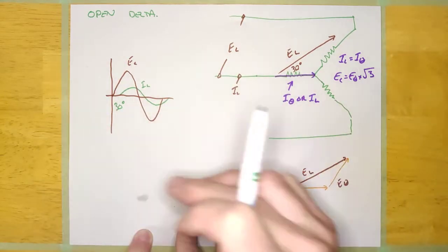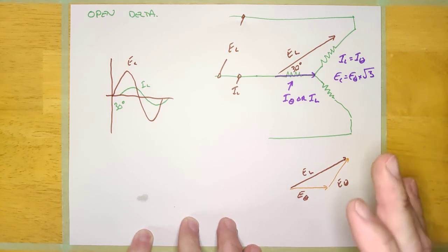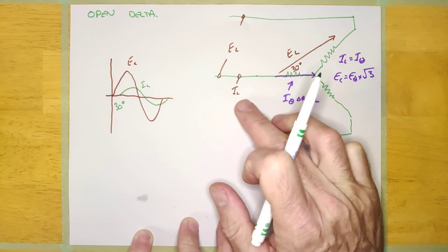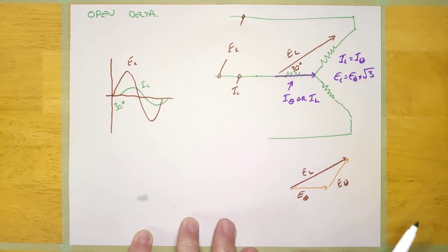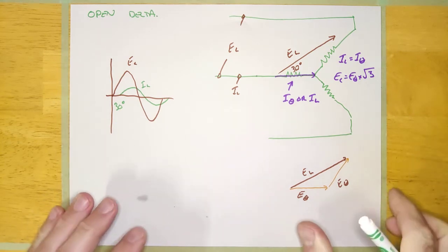And the people who are supplying us energy, guys, they don't care about the phase angle in the lines. They care about their phase angle where it is being generated, okay? So really quick here, guys, what's happening is a three-phase load that is in phase will cause the line voltage and the line current to be out of phase by 30 degrees. All right, but it'll be back in phase in the windings of the transformer, out of phase in the lines feeding that transformer, and in phase in the windings of the machine that's generating the voltage.